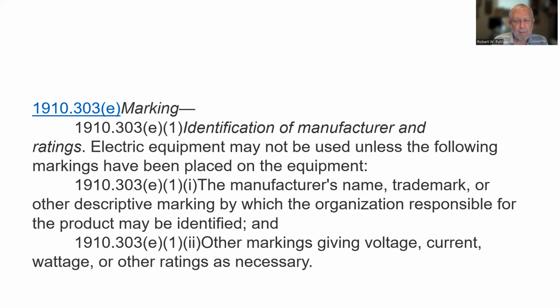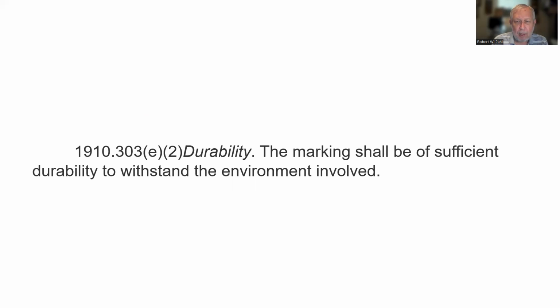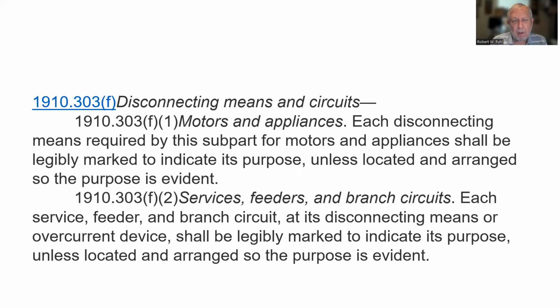Marking, identification of manufacturer and ratings. Electric equipment may not be used unless the following markings have been placed on the equipment: the manufacturer's name, trademark, or other descriptive marking by which the organization responsible for the product may be identified, and other marking giving voltage, current, wattage, or other ratings as necessary. The marking shall be of sufficient durability to withstand the environment involved.